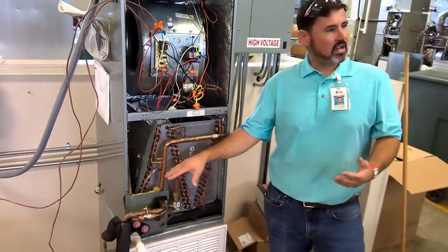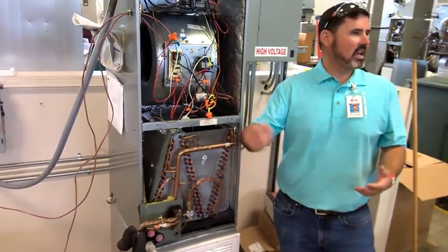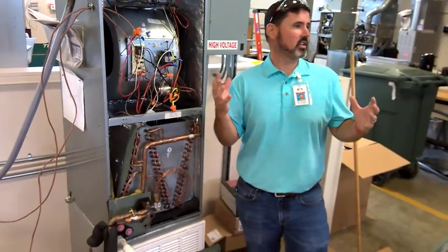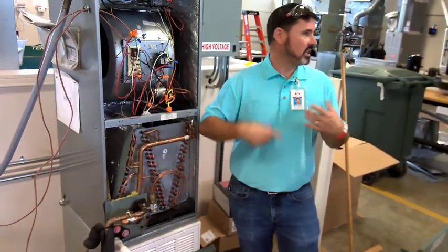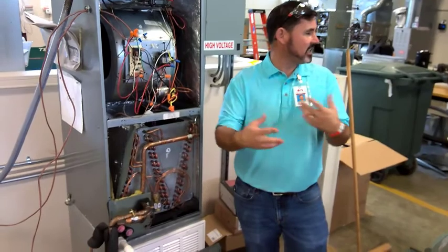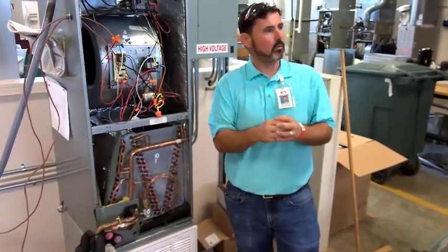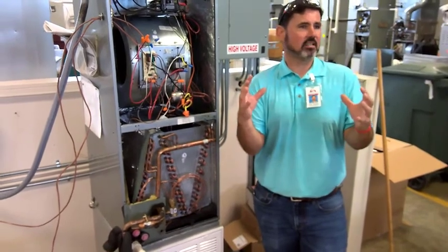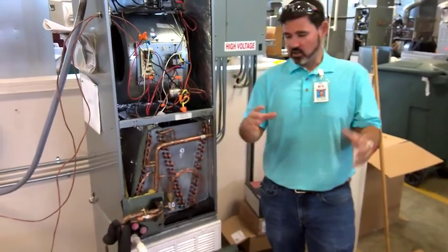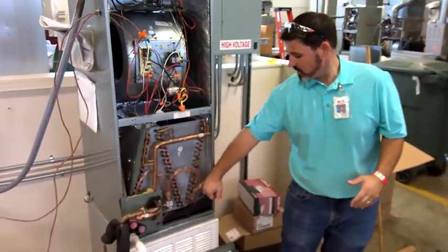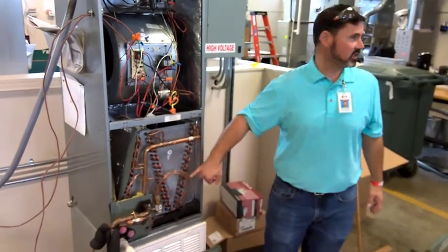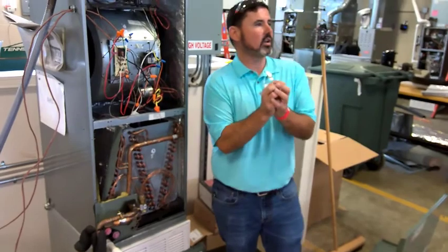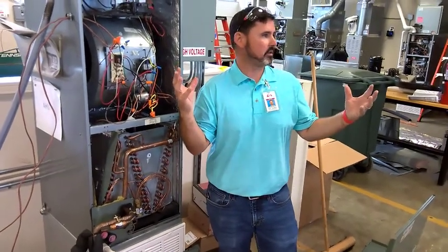One cool thing about it is, no matter how much heat you add to it, as long as you've got liquid going to a vapor, you're not going to change the temperature in it. So you can keep adding heat, adding heat, adding heat. As long as that liquid is changing to a vapor, it's using all of that heat you're adding just to change states, and it's never changing its temperature. So if it starts off at 40 degrees right here, it's still going to be 40 degrees here, and it's still going to be 40 degrees here, until at some point I no longer have any liquid left to evaporate.